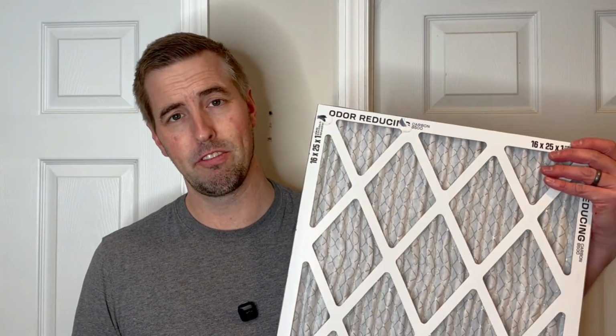So ultimately, after going through this testing, I've pretty much confirmed that my furnace is really only going to be able to handle the cheapo MERV 2 fiberglass filters. Maybe I can get up to a MERV 3, 4, 5. I could test that. But these pleated filters that are up in the MERV 8, 11, 13 range are going to cause issues for my system.